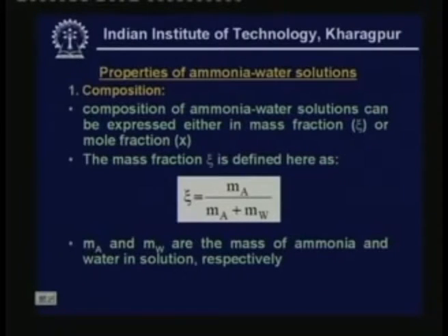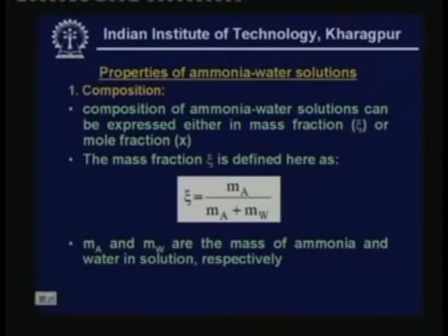Now let us begin the discussion with properties of ammonia water solutions. Similar to water lithium bromide solution, we can define composition of ammonia water solution in terms of either mass fraction or mole fraction. However, there is one important difference: in water lithium bromide systems, the mass fraction and mole fraction are defined in terms of the mass or moles of lithium bromide — that is, on the basis of the absorbent. Whereas in ammonia water systems, the mass fraction and mole fraction are defined on the basis of ammonia, meaning they are on the basis of the refrigerant.